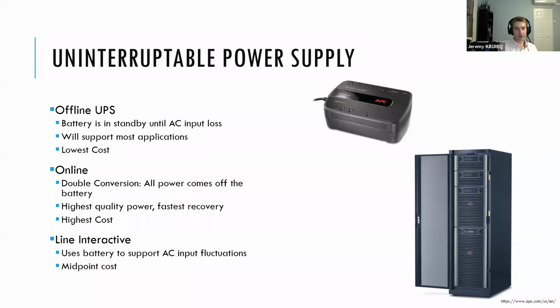When we get into the three main types of UPSs, because you can see, okay, what's the difference, you're talking about these really expensive ones, but then I can go into Staples and buy a computer UPS. So what's the difference? Your most basic UPS, this is what you see in consumer products mostly, is what's called an offline or standby UPS. And that is essentially a battery backup, if we think about it. It's got an AC charging circuit, charges that battery inside the unit. And when it senses input power loss, it switches over to the battery and obviously converts back to AC.